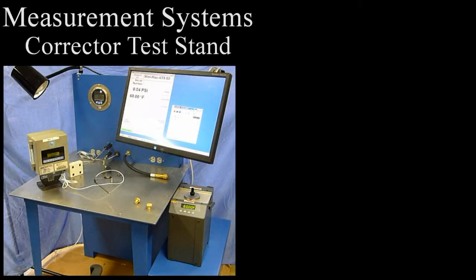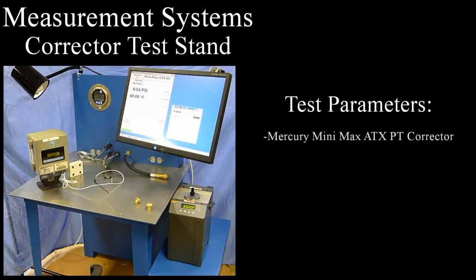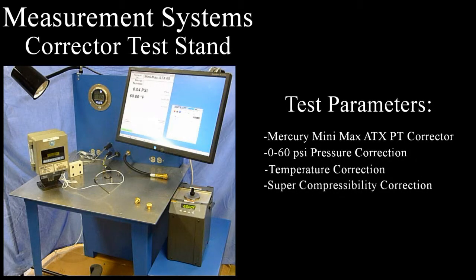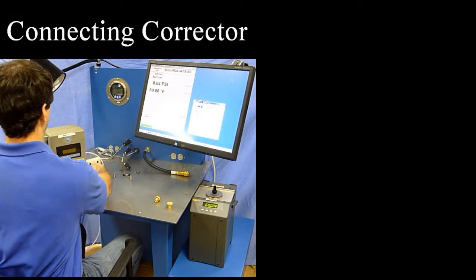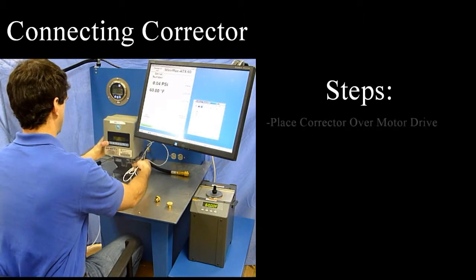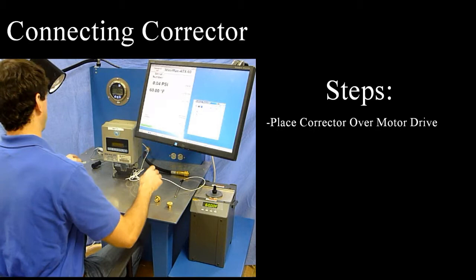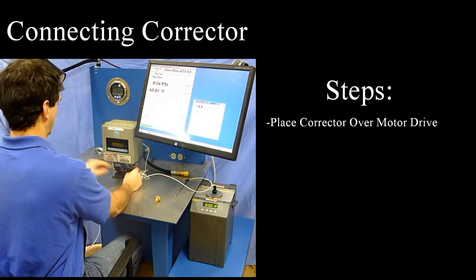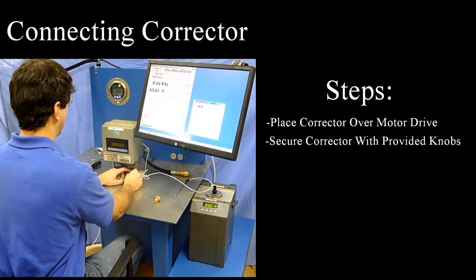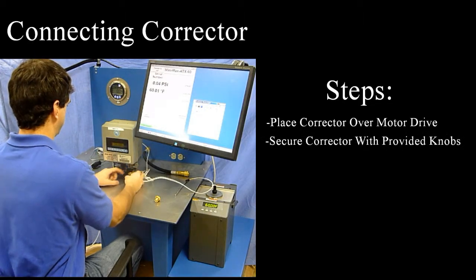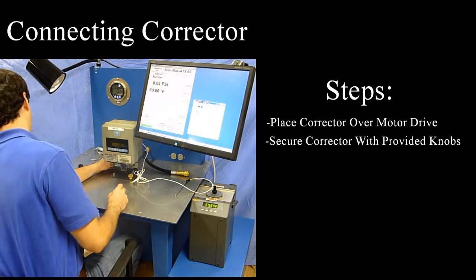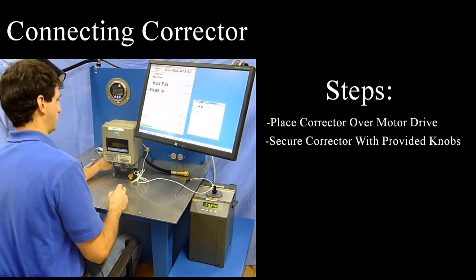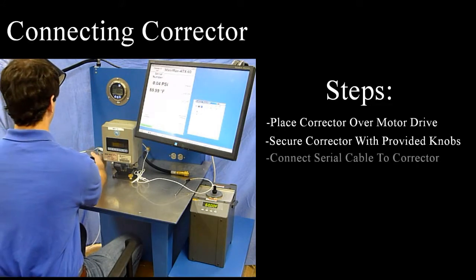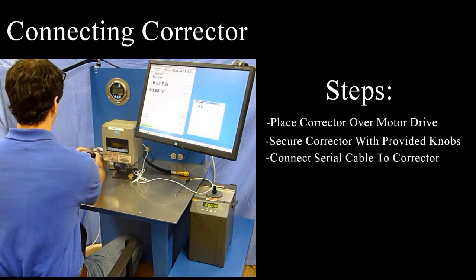To demonstrate the capabilities of the test stand, a Minimax PT 0 to 60 psi corrector is selected. The operator places the corrector over the stand's mounting studs and secures it to the stand with supplied thumb nuts. The operator connects a serial cable to the corrector for communications with the on-stand computer.